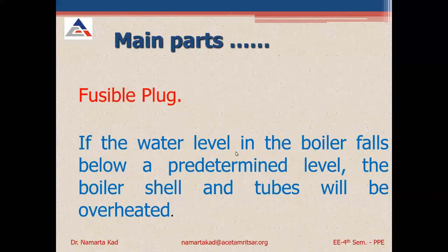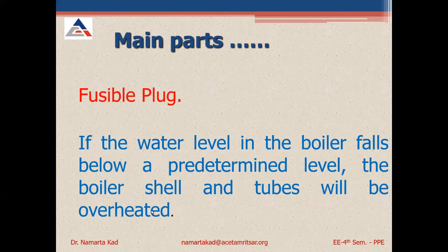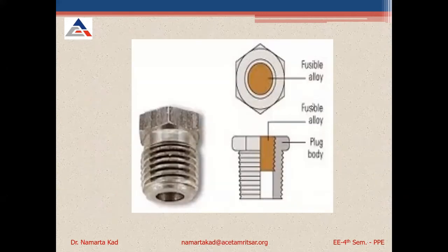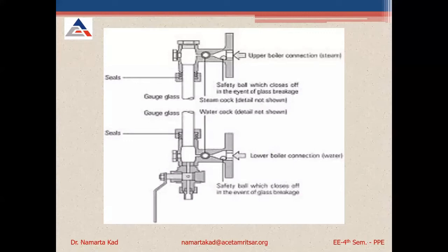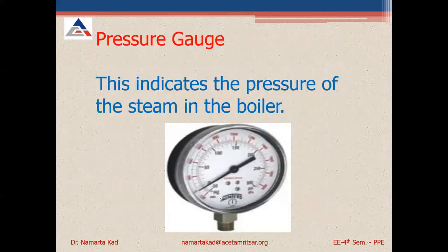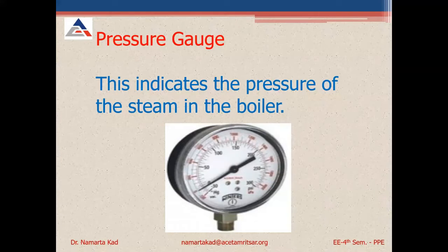Now let's look at different boiler components and how they appear. The fusible plug — also present in the Cochran boiler — prevents overheating if the water level falls below a predetermined level. The water level indicator shows the water level in the boiler. The pressure gauge is an analog meter-type instrument with a needle that indicates steam pressure inside the boiler in bars.